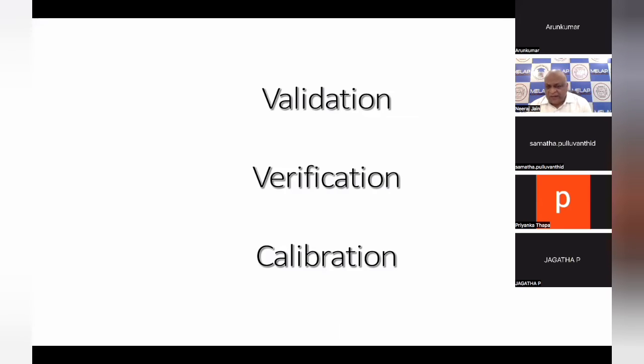Non-analytical measurements and analytical measurements. Non-analytical measurements are like speed in a centrifuge, volume in your pipette, temperature in your thermometer, or when you are measuring some weight. Everywhere measurement should be correct. Otherwise, these things will affect our results. What is required?